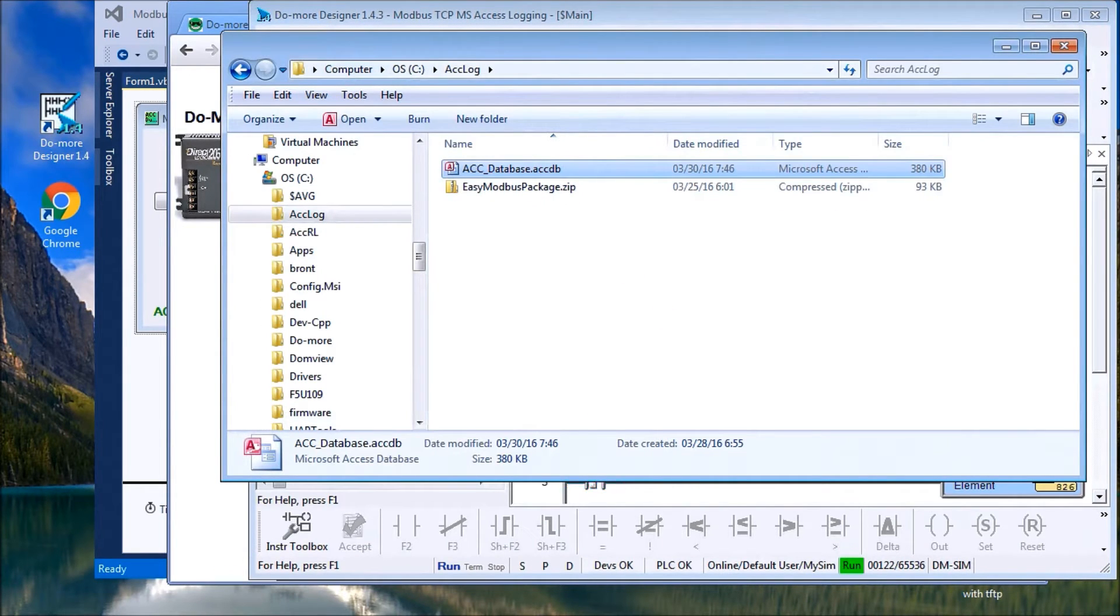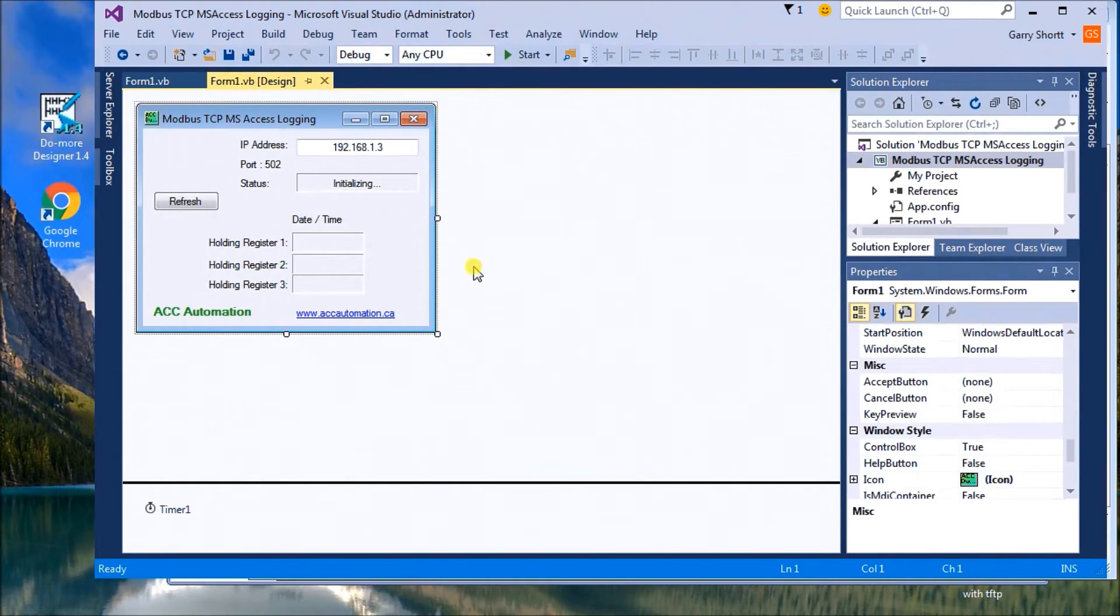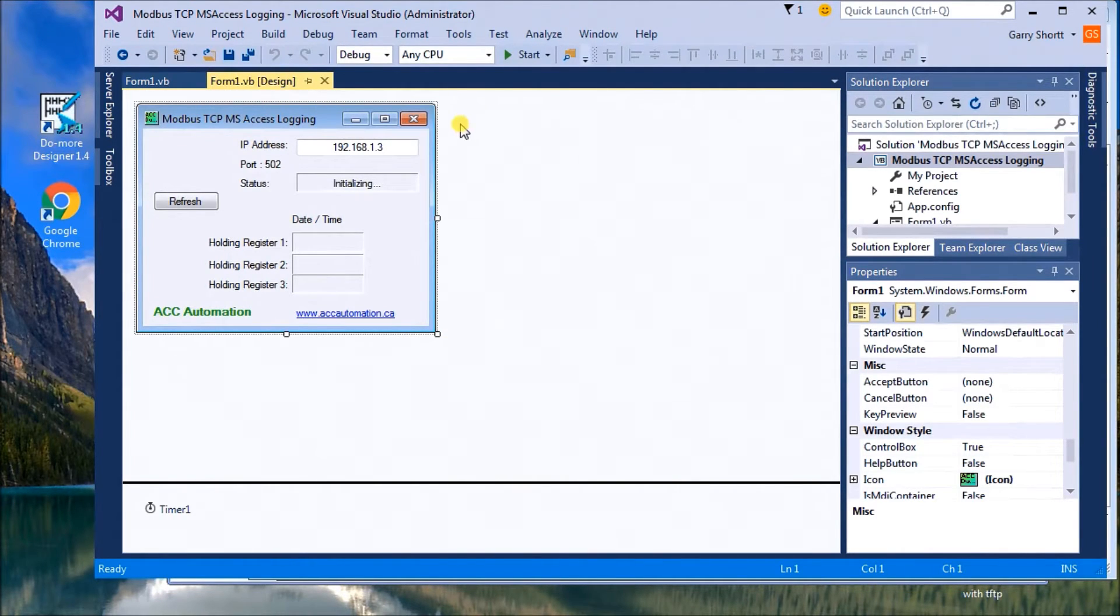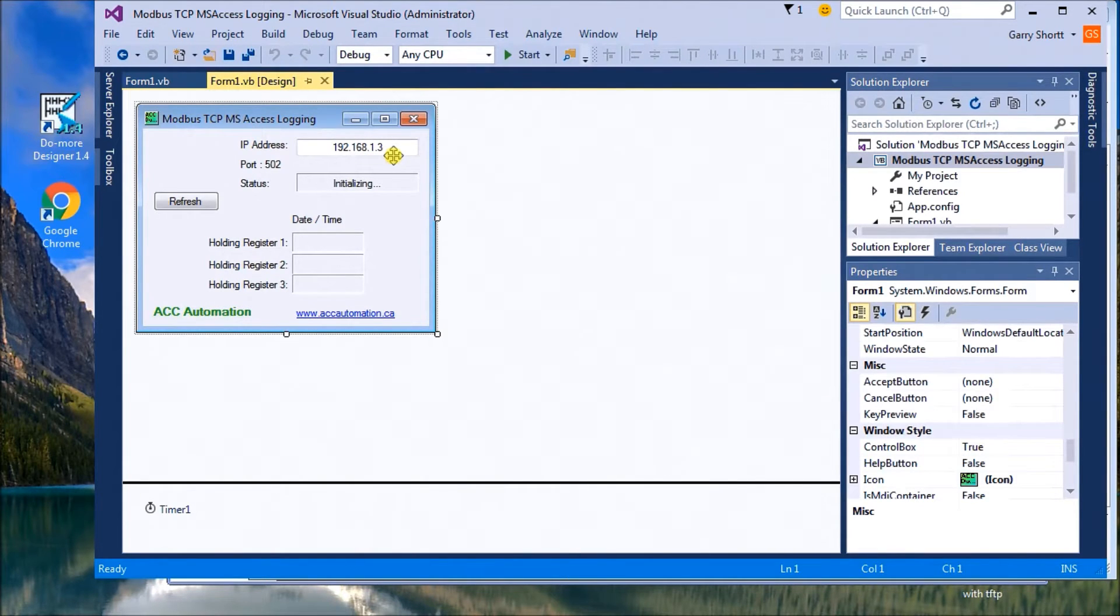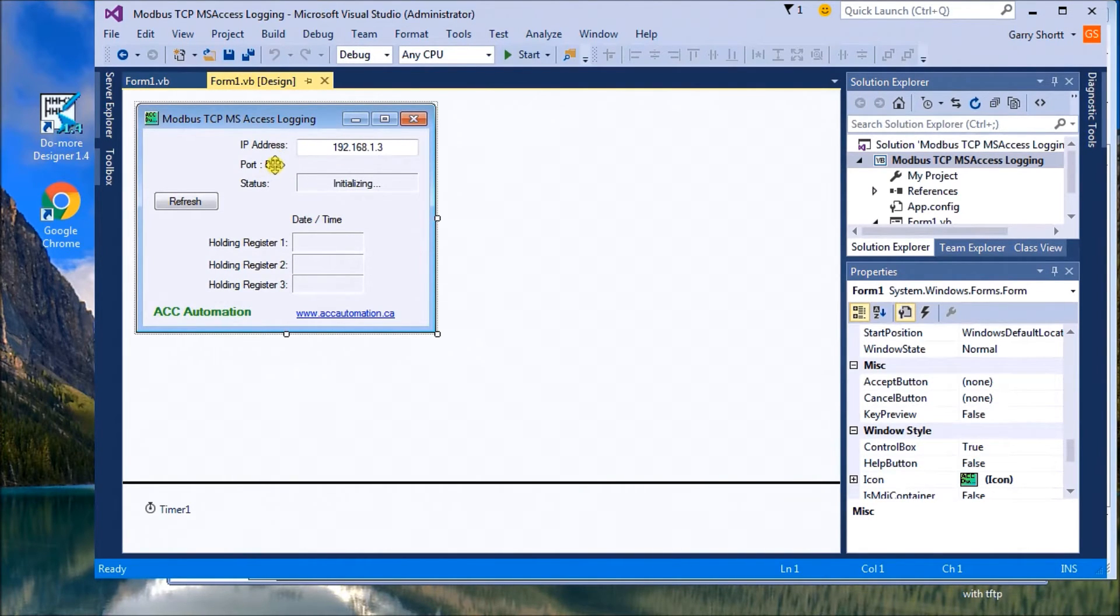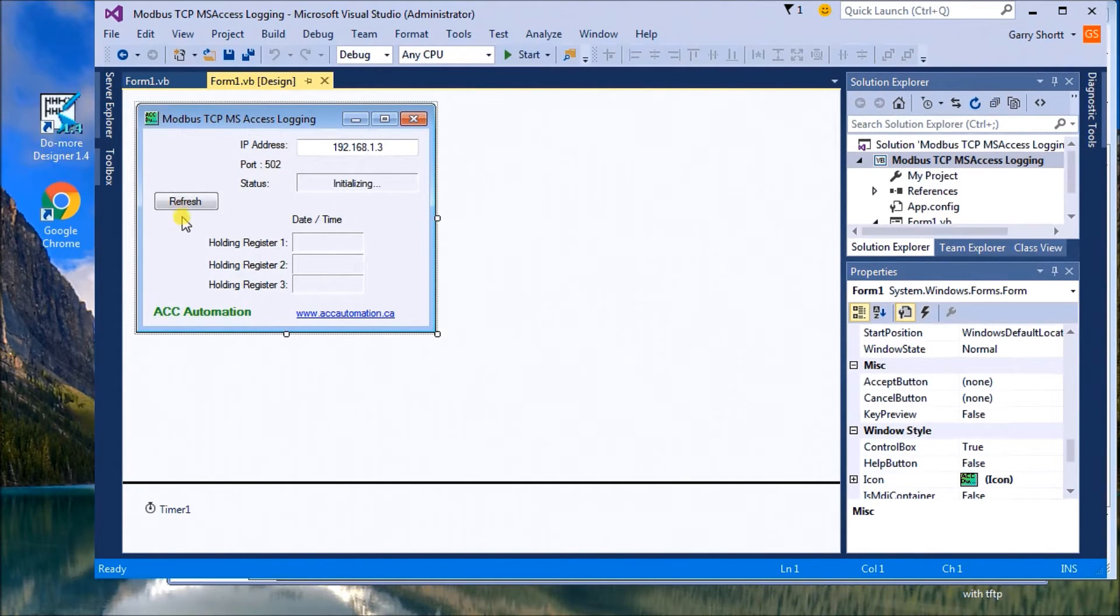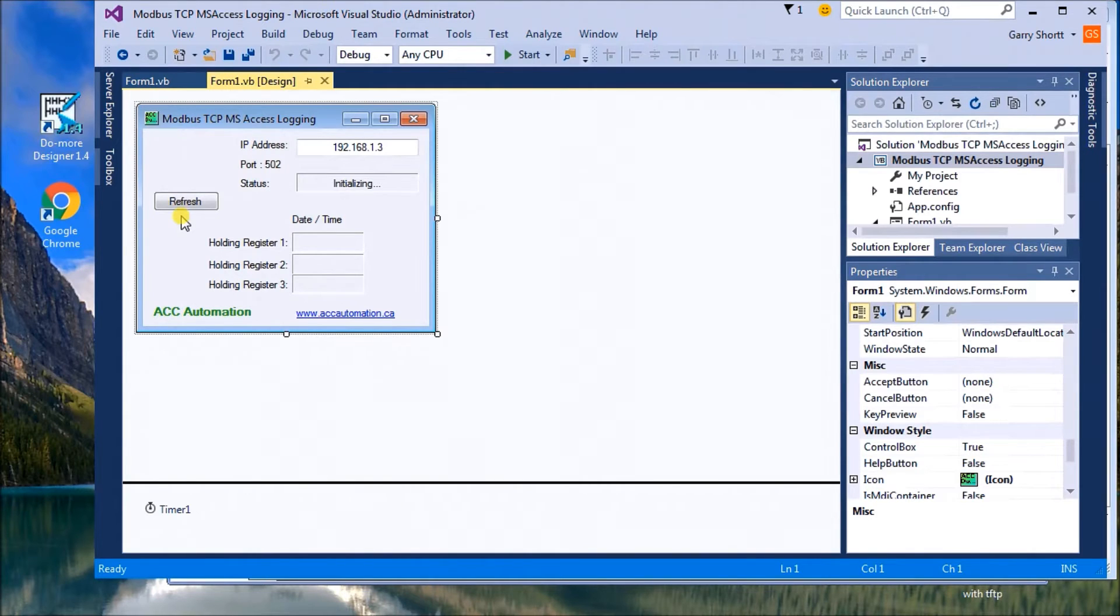And the next thing we'll do is we will call up our Visual Studio. And right now I have a form up here. And how the program will work is I will take this IP address which corresponds to the IP address on the Modbus TCP network. And always they use port 502 for it. And what we'll do is we'll grab that information when we hit refresh. So we'll have a button here called refresh. It'll grab the information and log it any time we hit that button.